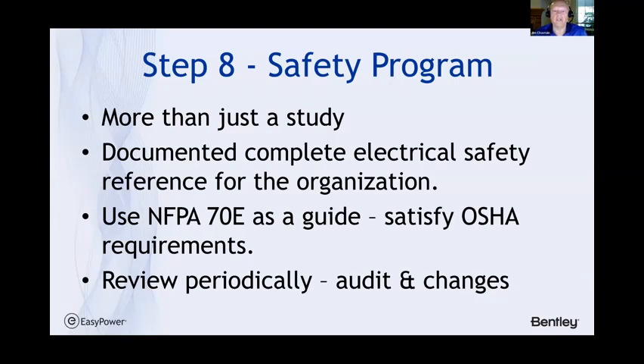Using NFPA 70E as a guide will help satisfy the OSHA requirements. It's not a legal document. So if you have a better way of protecting your workers and educating them, then by all means do it, but make sure you document what you've done and how that is enforced. And then the system should be reviewed periodically and be able to accommodate changes both in the standards and in the facility equipment. And then you should have an audit system that verifies the procedures are being followed.